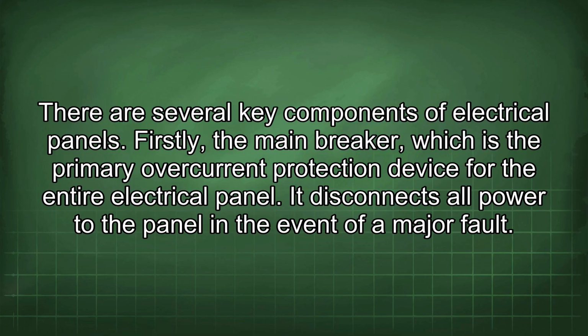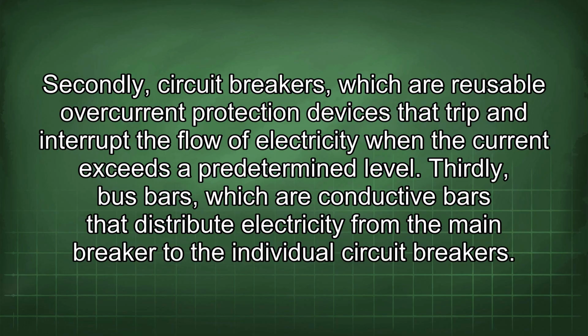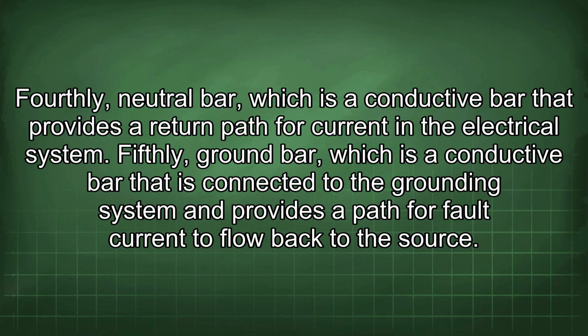Firstly, the main breaker, which is the primary overcurrent protection device for the entire electrical panel. It disconnects all power to the panel in the event of a major fault. Secondly, circuit breakers, which are reusable overcurrent protection devices that trip and interrupt the flow of electricity when the current exceeds a predetermined level. Thirdly, bus bars, which are conductive bars that distribute electricity from the main breaker to the individual circuit breakers. Fourthly, the neutral bar, which is a conductive bar that provides a return path for current in the electrical system. Fifthly, the ground bar, which is a conductive bar that is connected to the grounding system and provides a path for fault current to flow back to the source.